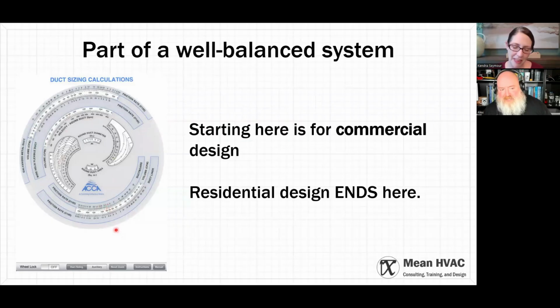I was taught this is how much air is in a duct. Well, commercial guys do it that way because they just change how big the blower is at the end of the day—they size the duct the same way every time. If they create a crazy duct system, they use a bigger blower; if they create a simple one, they use a smaller blower. But in residential, your blower is your blower—you don't have a lot of options. There are some, but the options in commercial are wide, and in residential they're limited.